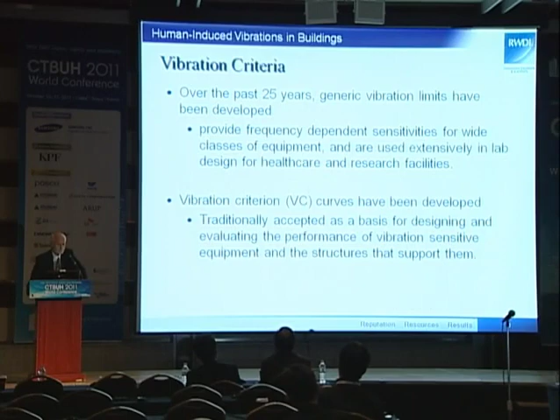The top-level curves are appropriate for areas where what's going on is not particularly sensitive to vibration. The traditional method is to divide the frequency range into 1/3 octave bandwidths, and the ISO criteria, those top 4 curves, are expressed in that format. These are in units of micro-inches per second.